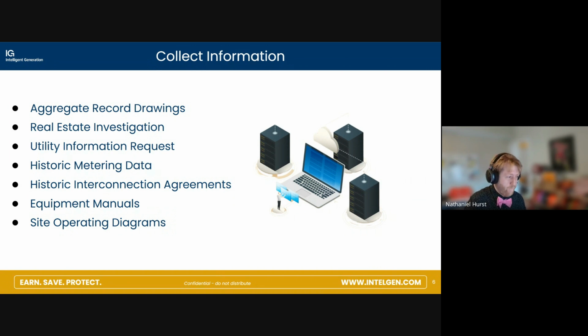And then lastly, site operating diagrams. Again, with heavier commercial and industrial sites, not every site is as simple as flipping off the main breaker and everything de-energizes. Sometimes you flip off the main breaker and a generator automatically turns on. Sometimes you switch off the main breaker and a second utility power line engages. Site operating diagrams are really important.